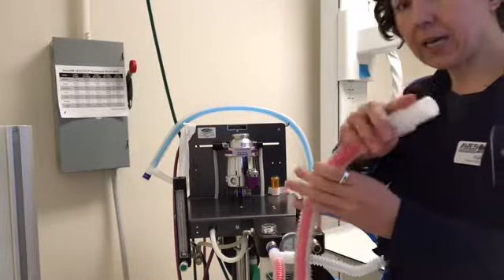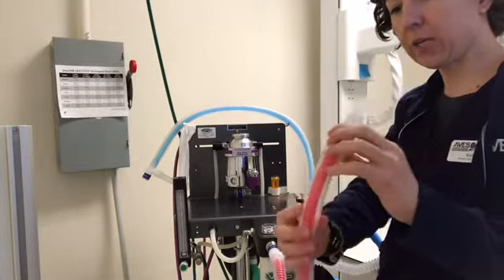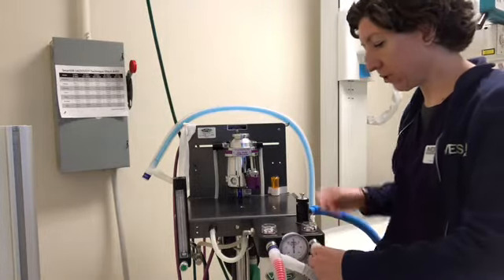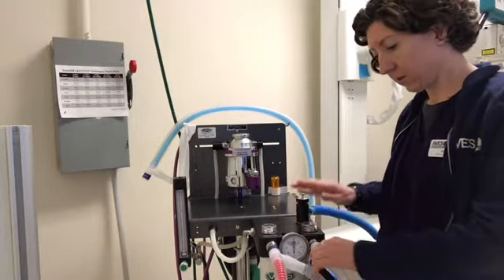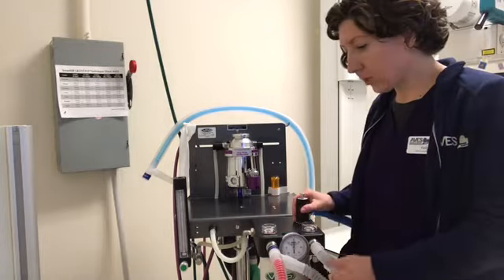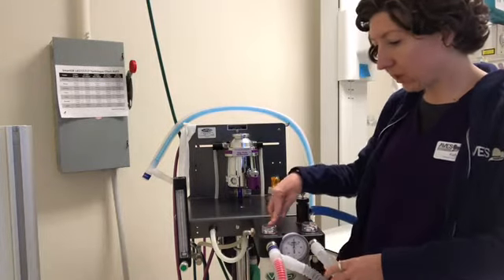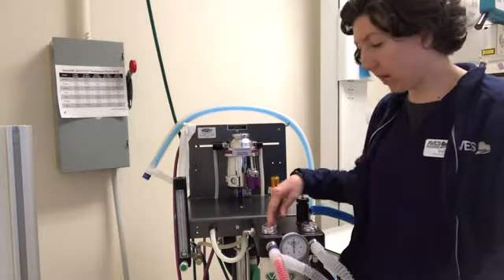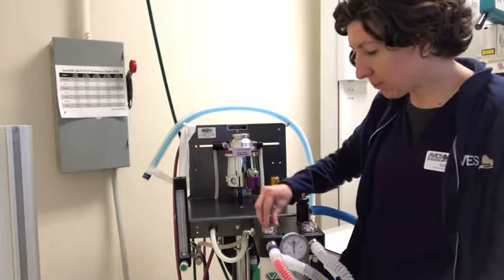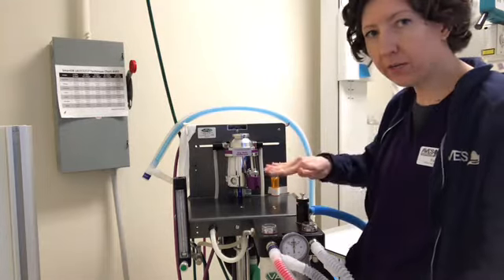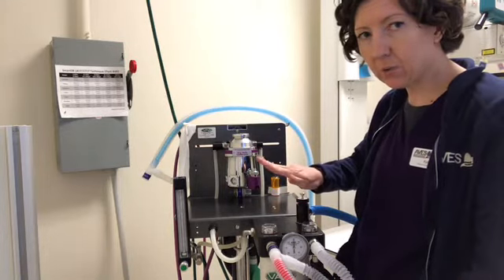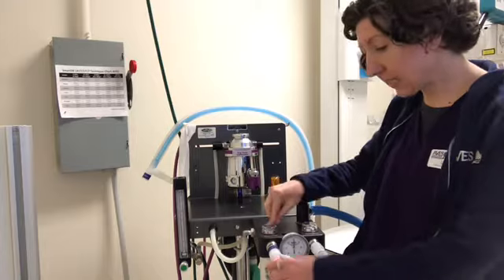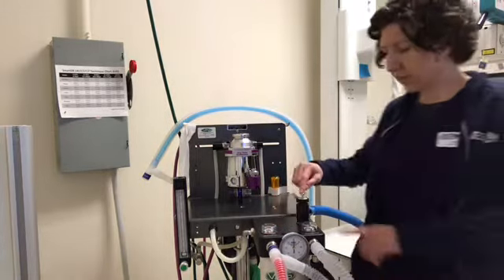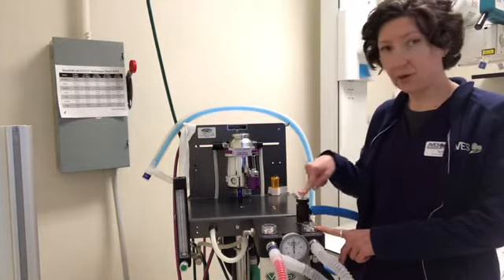As the patient exhales, it comes back through here and goes through the little, more like a T port, that goes into the exhalation unidirectional valve. And one of the ways you can tell if the patient is taking a breath is this piece at the top. When the patient takes a breath, it'll raise, so you can visibly see when that breath is taken. This is the pop-off valve.